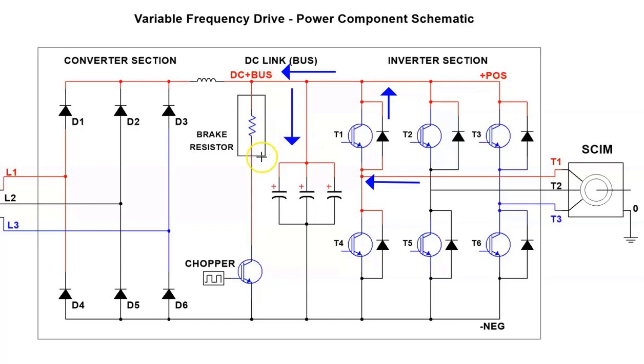Now, we have a braking resistor and a chopper circuit installed, and it will sense the DC bus voltage. It will turn on and send the energy out to the braking resistor. Not all drives have this circuitry. You have to spend a little bit more money to get this circuitry.